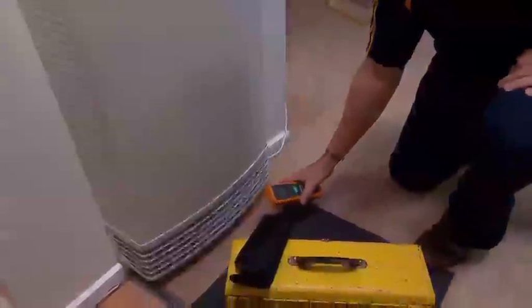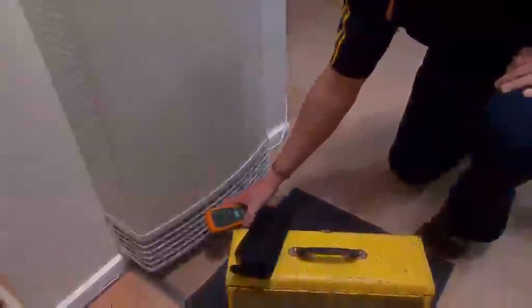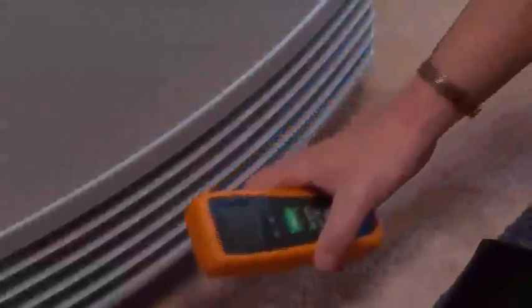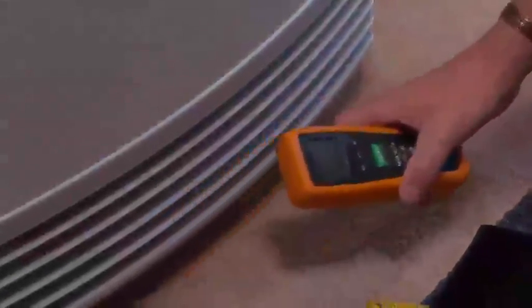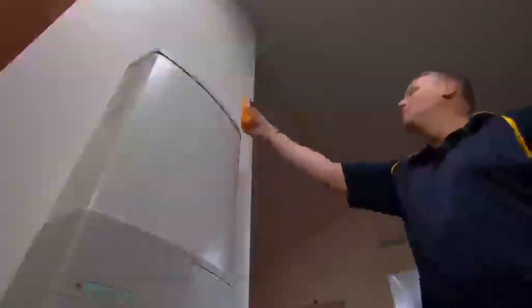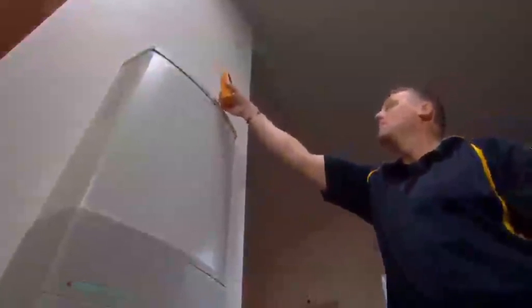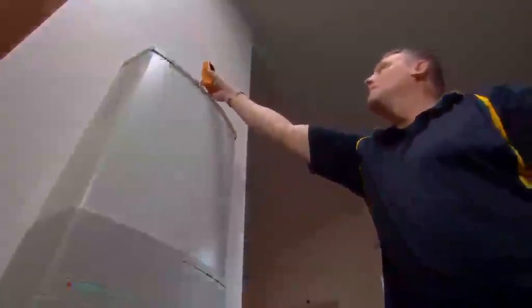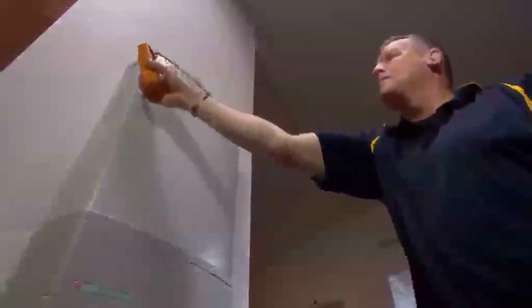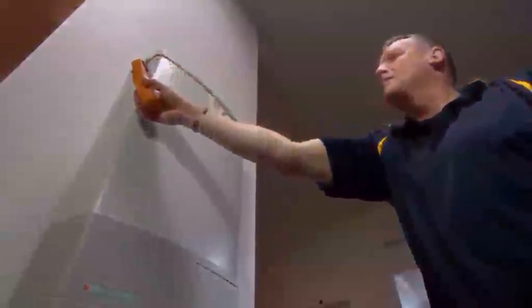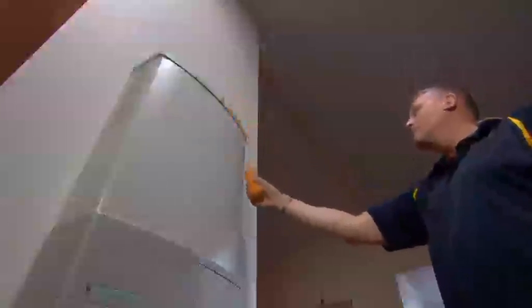Continue monitoring for leakage or spillage, and, in particular, note the readings taken after the appliance has been operating for 5 minutes. When sampling at the draft diverter opening, please ensure that the sampling probe is positioned adjacent to the opening and not inside the draft diverter. A CO reading will more than likely be evident when the flue is cold. It may take some minutes for the flue to draw properly.